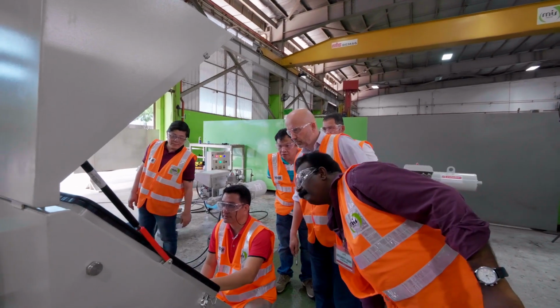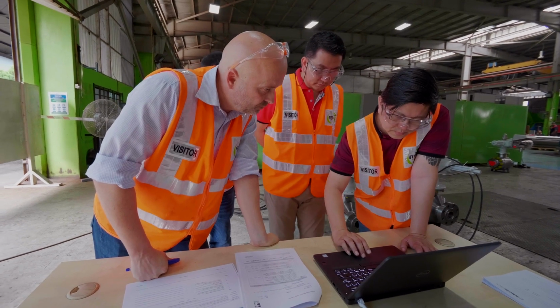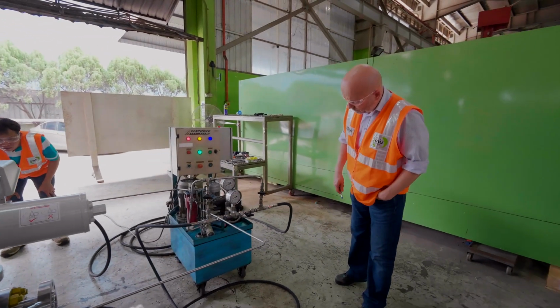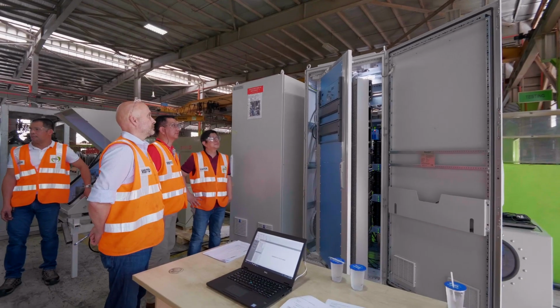During the validation testing, all the components that have been delivered by the different companies are integrated in this factory, and during this week we are testing that the HIPS system works as specified. The validation is basically the last phase in our certification project. When the validation is finished, that basically means that everything is working as specified. Then the company can pack up the HIPS system and ship it to the field where the end user can install it and start using it.